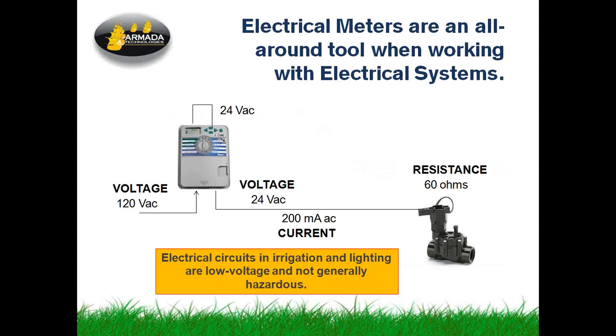Next, the kinds of electrical systems we're working with are very low voltage, and the voltages are not hazardous. They aren't going to cause a fire. They aren't going to hurt anyone. So the voltages we're dealing with are 24 volts AC, and resistances are on the order of 60 ohms, and a quarter of an amp type of currents. Very, very small things. The only things that are hazardous here are 120 volts AC. So that's the only place that caution is really required.